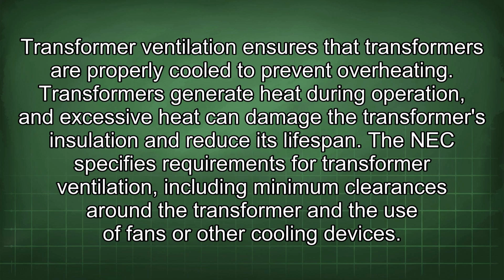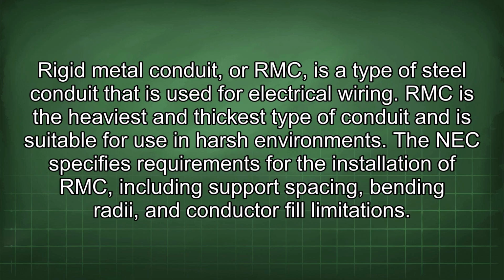cooling devices. Rigid metal conduit, or RMC, is a type of steel conduit that is used for electrical wiring. RMC is the heaviest and thickest type of conduit and is suitable for use in harsh environments. The NEC specifies requirements for the installation of RMC, including support spacing, bending radii, and conductor fill limitations.